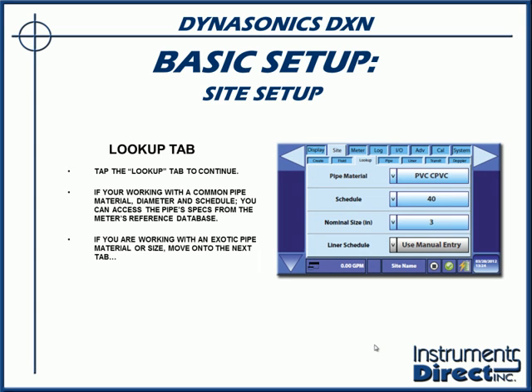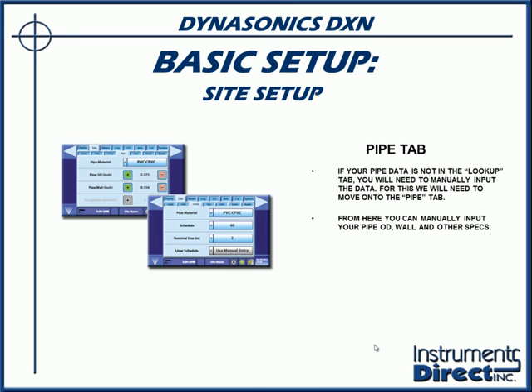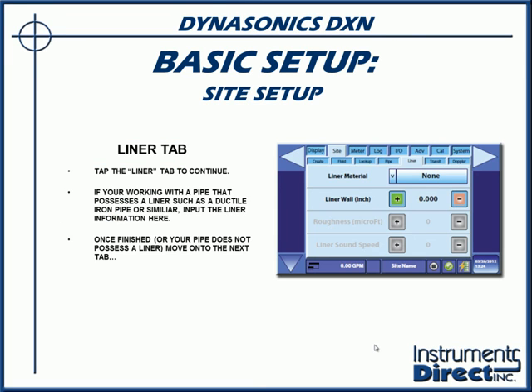Then the next step is to go into the pipe itself. There's a database. You can go in the lookup tab to actually populate the information. So if you have anything that's using an ANSI pipe chart that you know of, if you go in there and select the pipe material and the schedule, it'll actually pull up the pipe size information, or you can use a manual data entry system. So now that we have the pipe data in the system, and we have the process liquid in the system, then we can move forward.